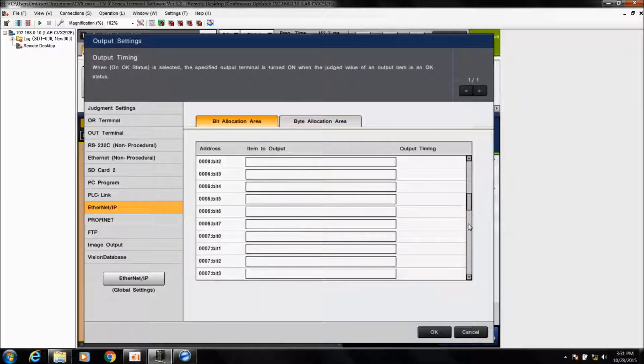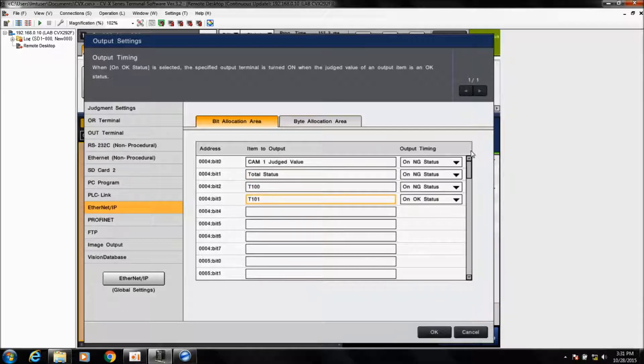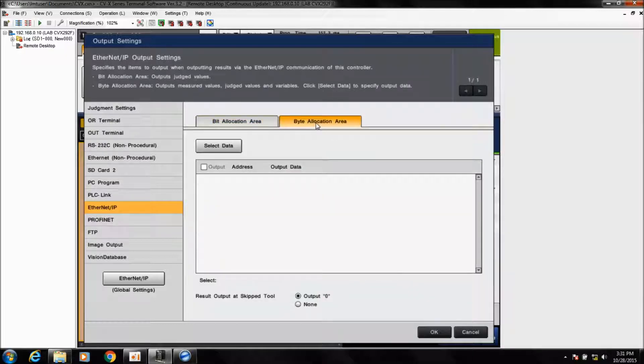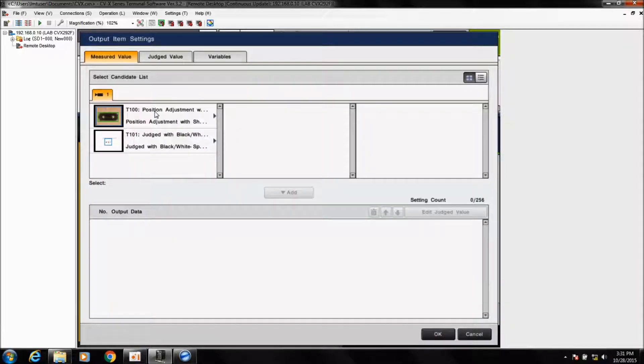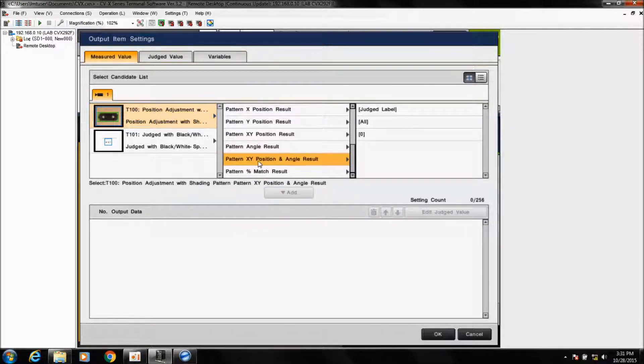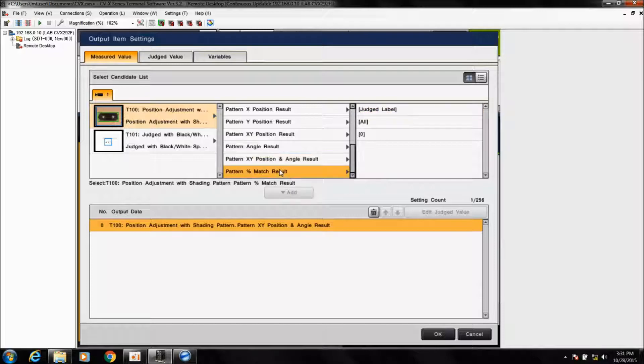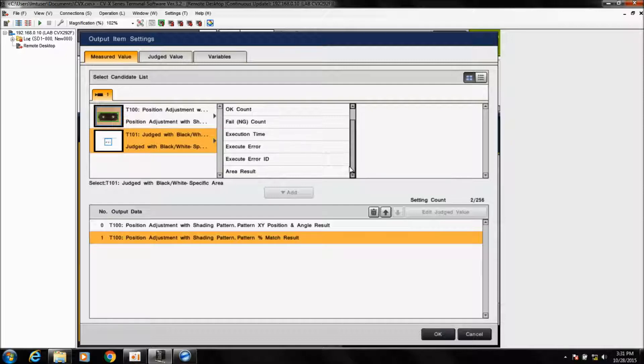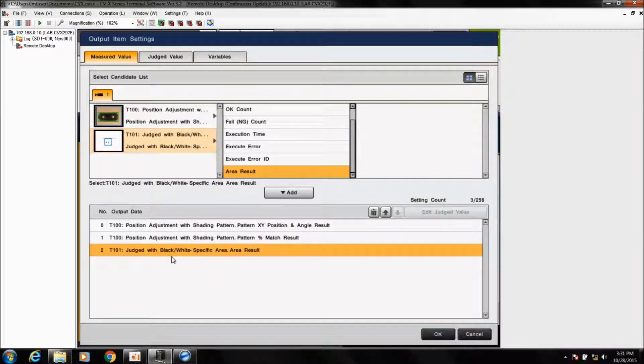The byte allocation area contains the measured results, such as X values, Y values, pixel counts, etc. To add items, come to this tab and click Select Data, choose the tool, scroll through the list, and pick the data item you want. In this example, we're going to output the X and Y position, angle result, match percentage from the pattern tool, and the pixel count from the pixel counting tool. These items will be output in order to the PLC over the Ethernet IP connection.